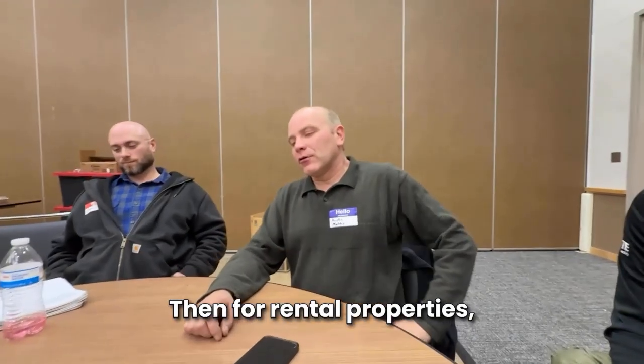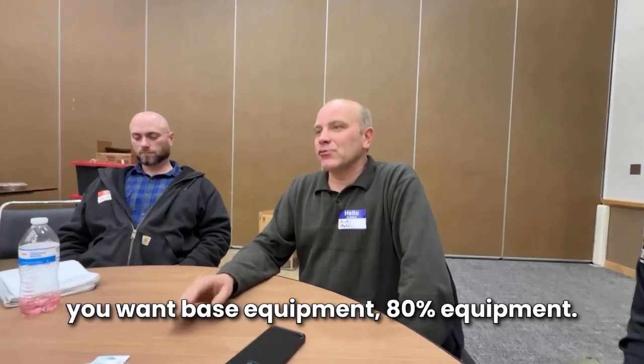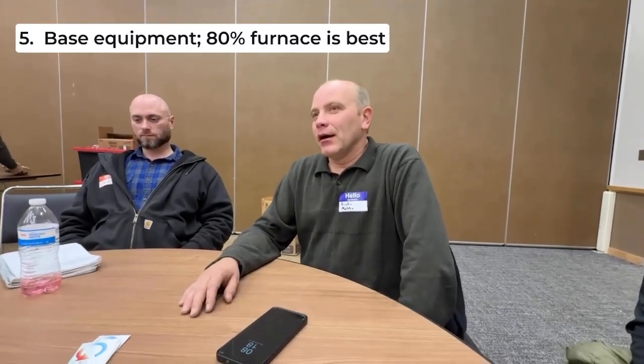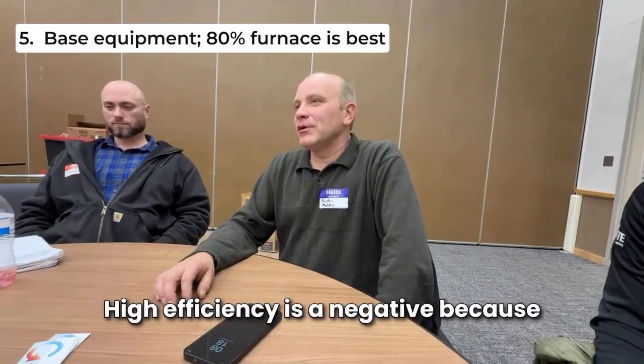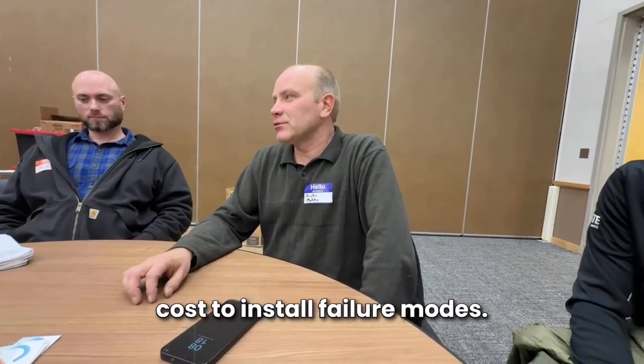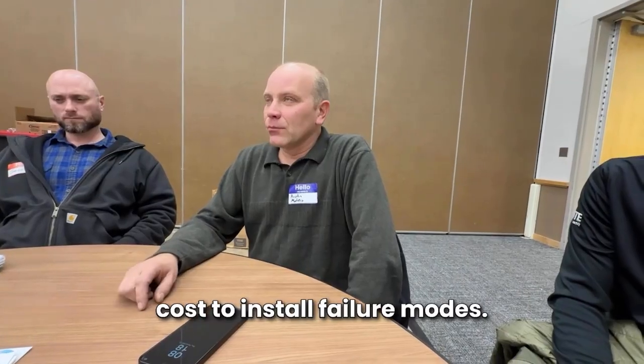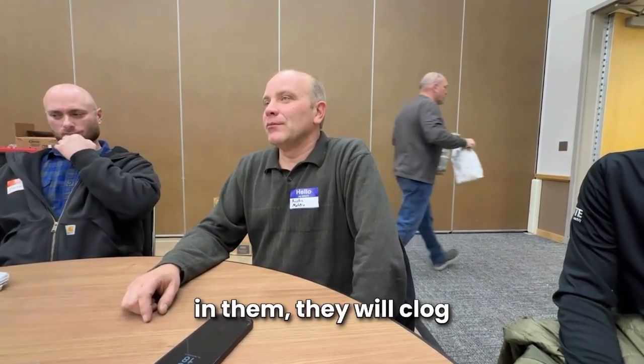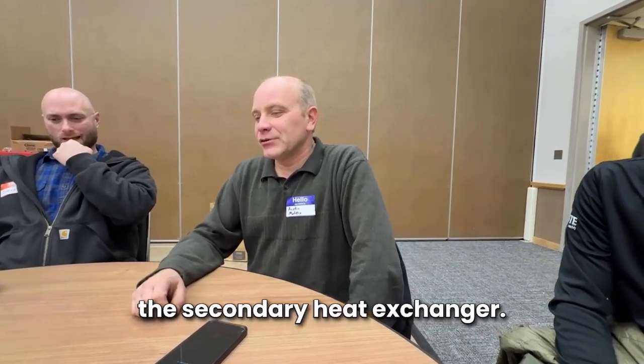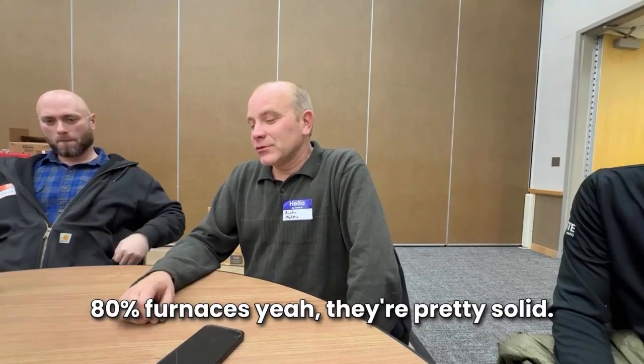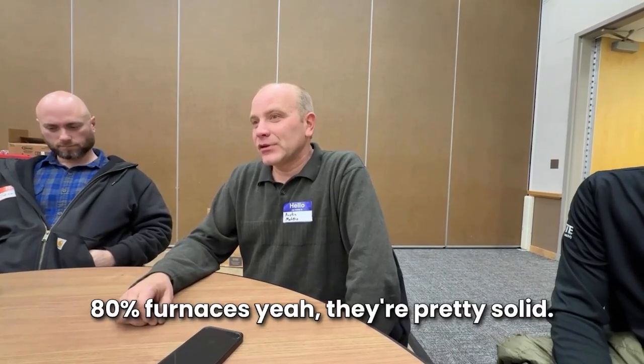For rental properties, you want base equipment, 80% equipment. High efficiency is a negative because you have a lot more failure points, costs to install, failure modes. If you don't run a filter in them, they will clog the secondary heat exchanger.